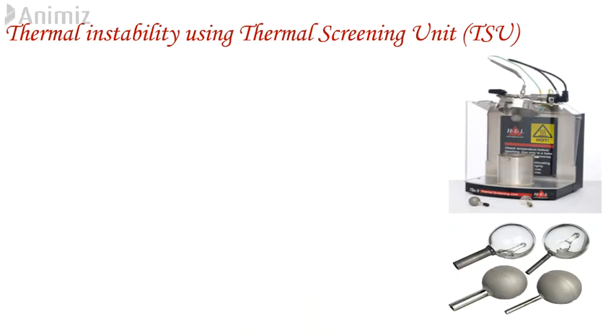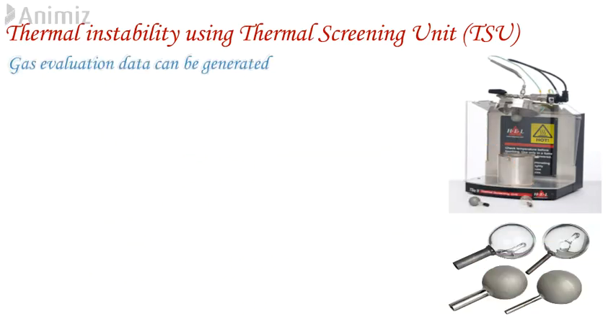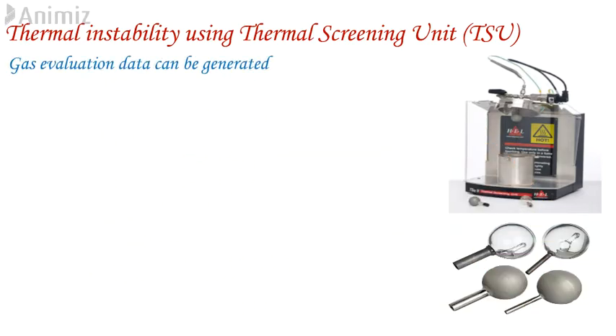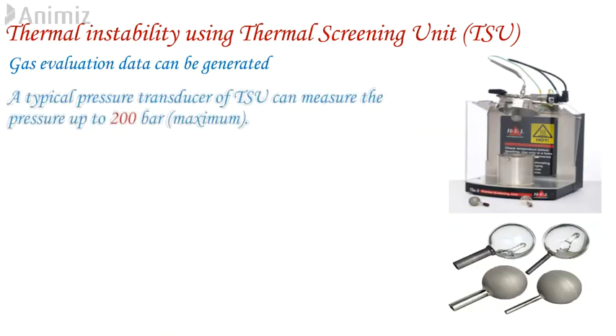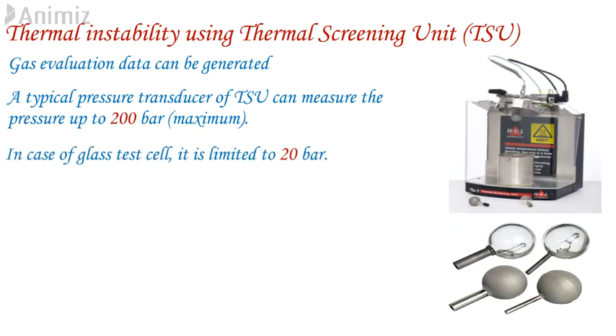Advantage of TSU over DSC: by using TSU, gas evolution data can be measured. A pressure transducer is connected and it records the pressure data constantly throughout the entire experiment. A typical pressure transducer of TSU can measure pressure up to 200 bar maximum. In the case of a glass test cell, it is limited to 20 bar.